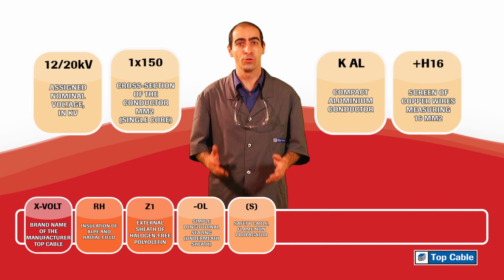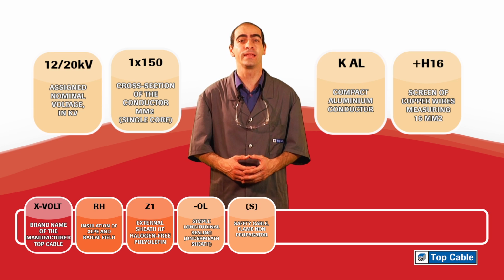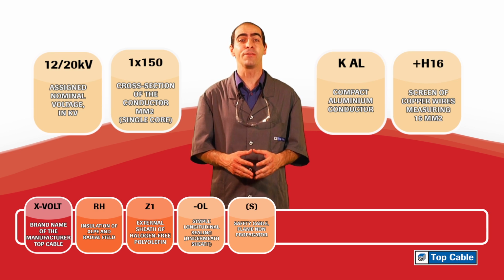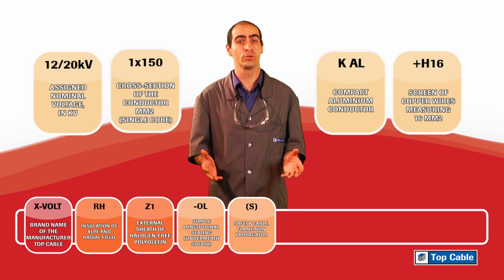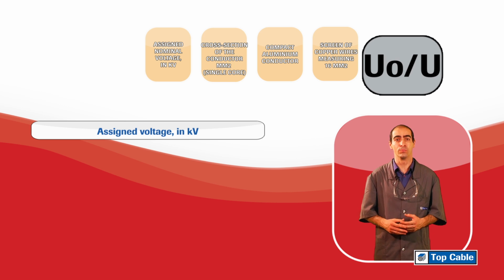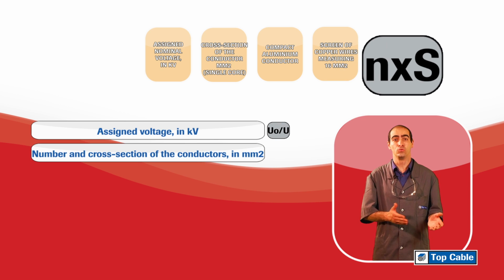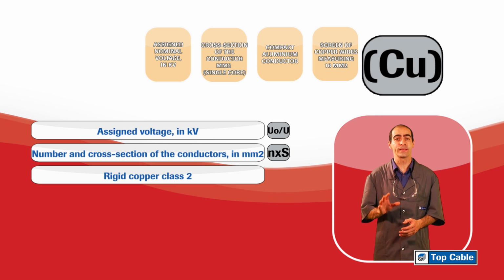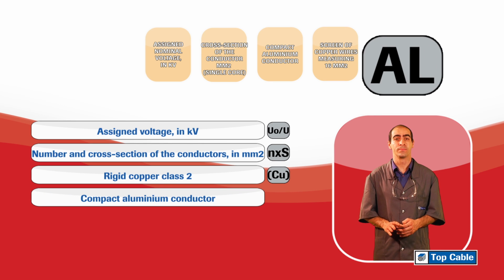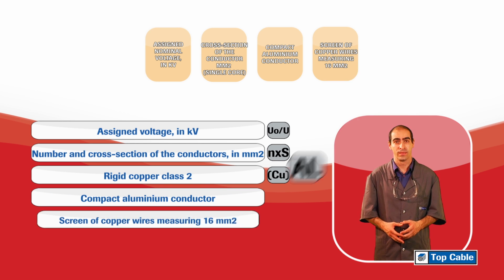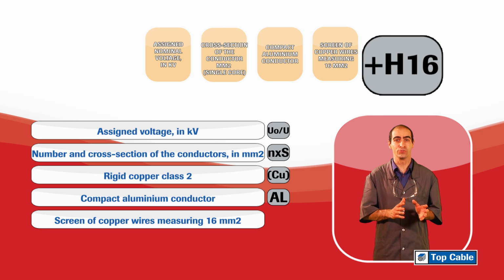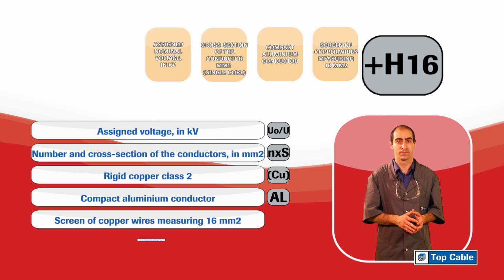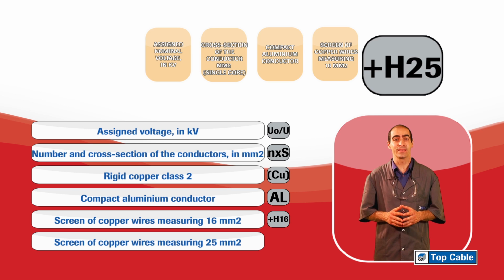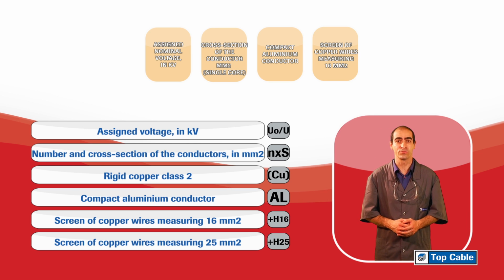The third block, 12/20 1x150 KAL plus H16 in the example, refers to the assigned voltage, the conductor, and the metal screen. UO/U, assigned voltage in kilovolts. NxS, the number and cross-section of the conductors in millimeters squared. In white, rigid copper class 2. AL, compact aluminium conductor. Plus H16, screen of copper wires measuring 16 millimeters squared. Plus H25, screen of copper wires measuring 25 millimeters squared.